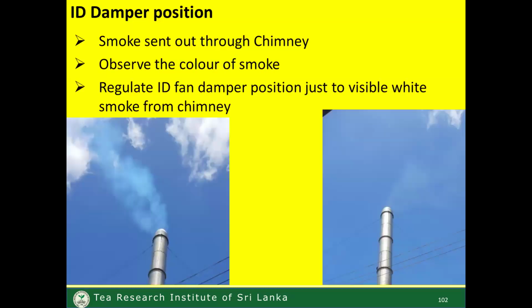I think it's too much for you if you are in a factory or tea estate, but these finer steps are helpful for you. Right here you can see an excess quantity of white, or almost white or blue color, smoke escaping through the chimney. Why is it happening, right? This means it needs more air for combustion. Therefore, we have to open the damper more than this position. Then it will facilitate having more air, and the escape of unburned particles will stop, right?